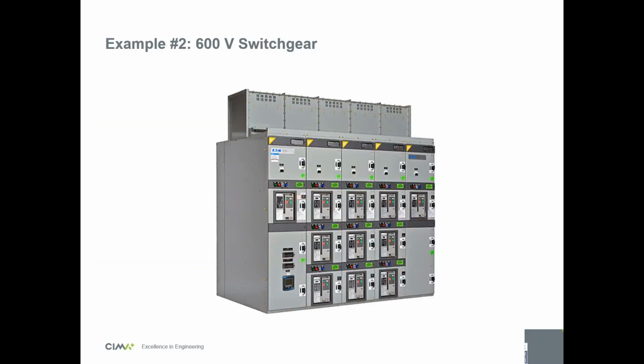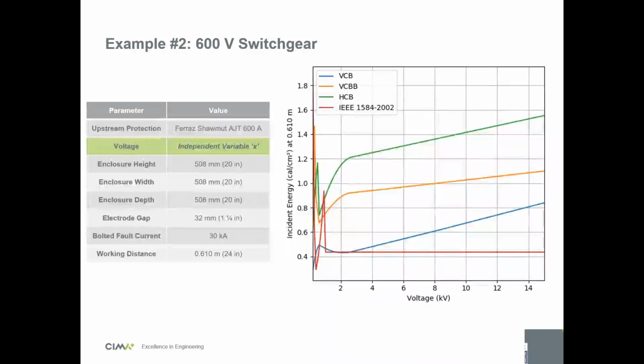So now example 2: if you have a 600 volt switchgear, what's going to be the impact? Now there's no 2-second rule. I've used a Ferraz Shawmut AJT 600 amp fuse. So you have to consider that the arcing current changes for every point on these curves, so the trip time will change also. Let's say we have the voltage plotted here. It's about the same relationship, but since our actual voltage is 600, it's hard to say with all these lines going up and down. It's hard to say what's worse.